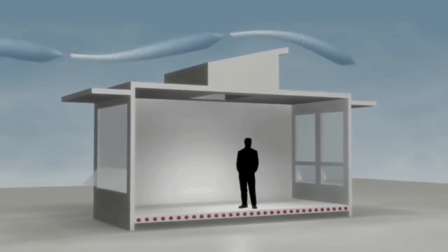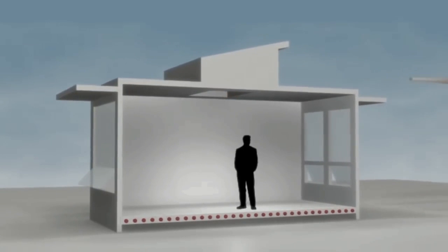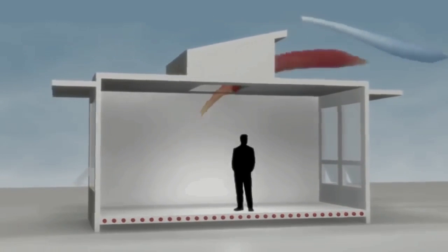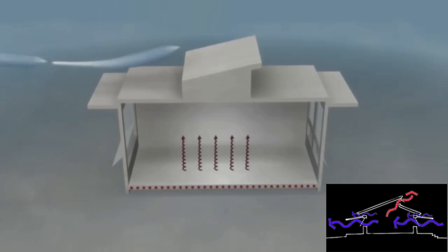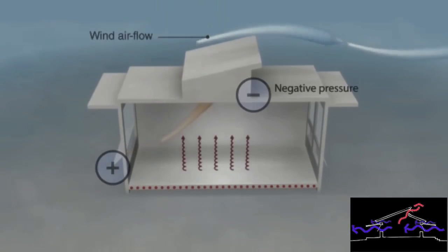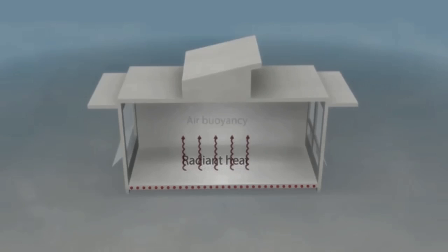Natural ventilation is the technique of using natural air movement from the outside and drawing it inside without the aid of a mechanical ventilation system. In this cross ventilation example, the negative pressure difference caused by the predominant wind direction airflow sucks the warm, stale air out of the high level opening, aided by the air buoyancy effect resulting from the upward rising radiant heat in the space.